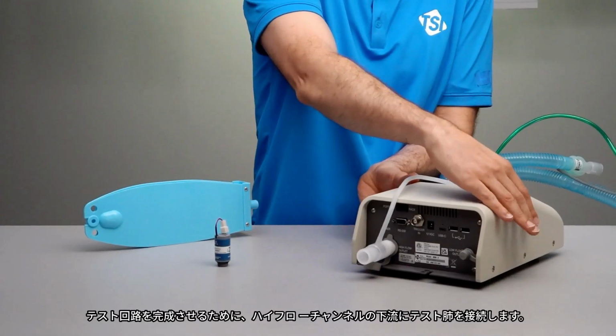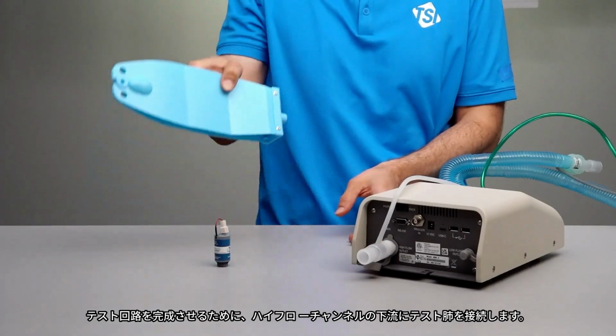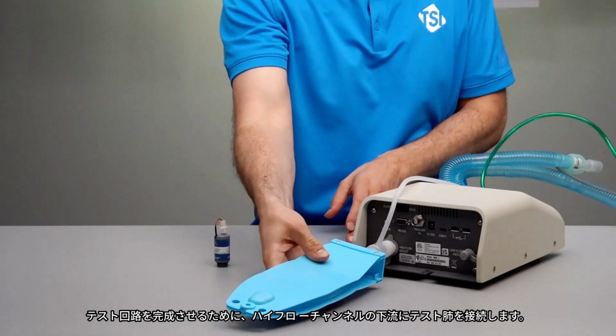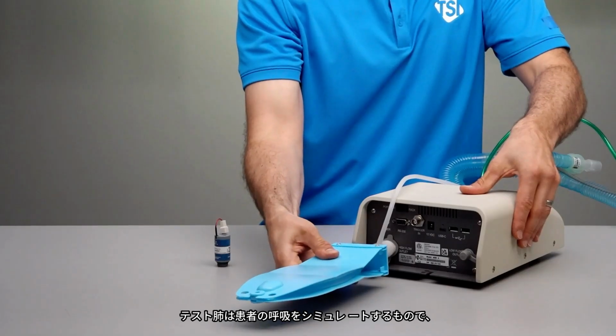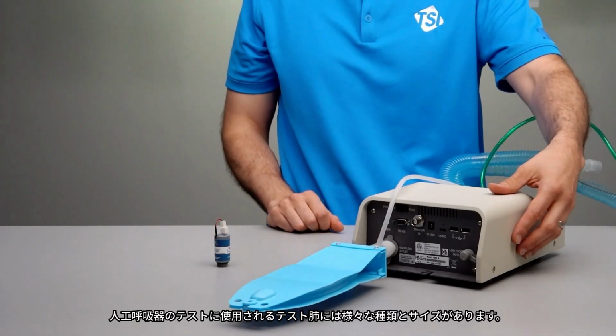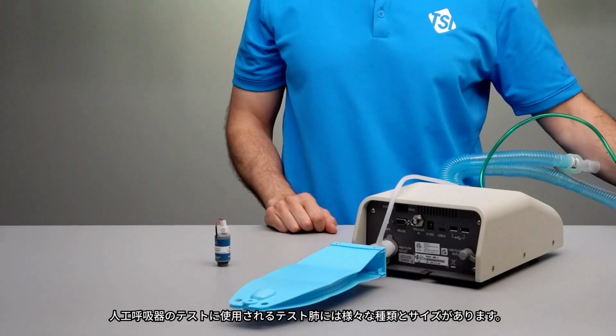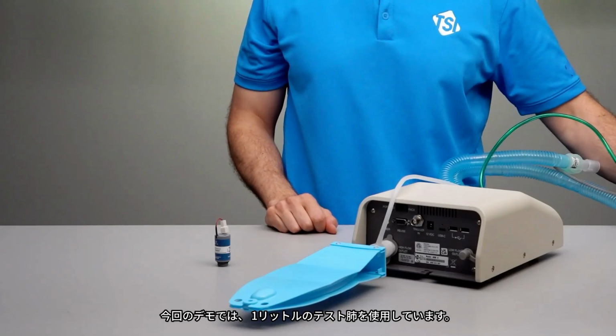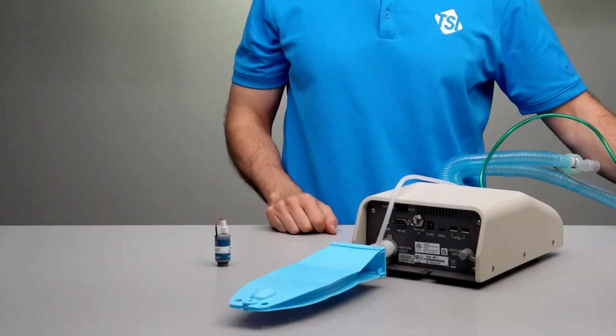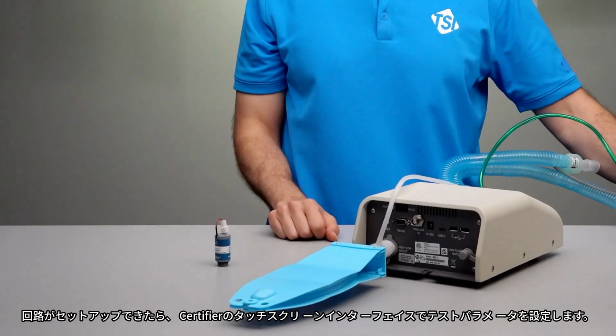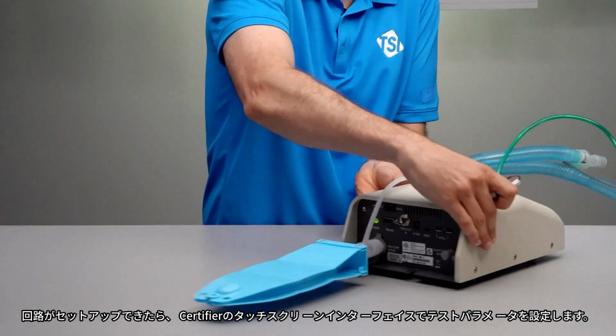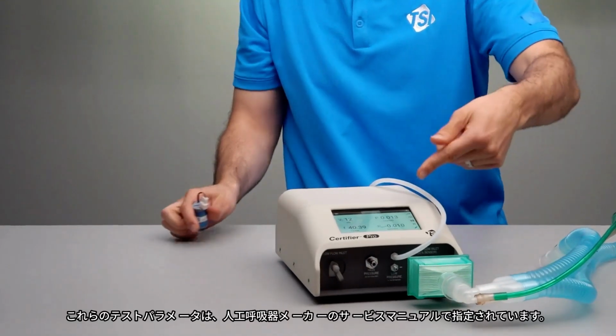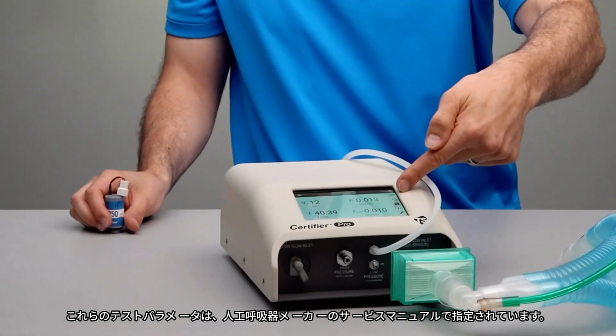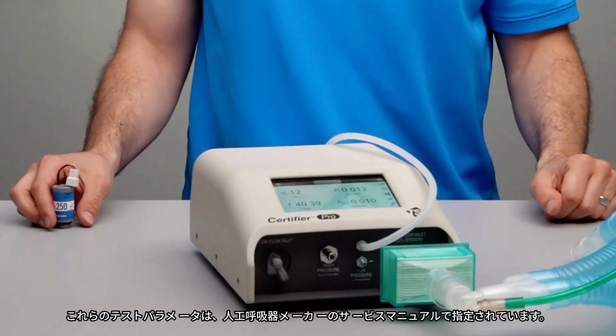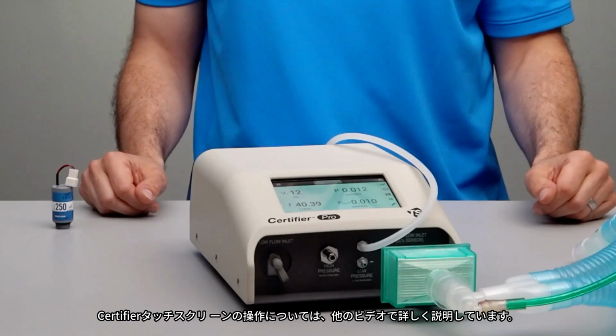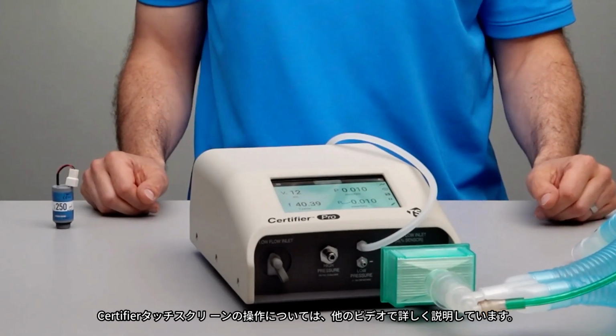To complete the test circuit, we will connect the test lung downstream of the high flow channel. The test lung simulates a patient's breathing, and there are a variety of different types and sizes of lungs that are used when testing ventilators. For our demonstration, we're using a 1-liter test lung. After the circuit is set up, you would configure the test parameters on the certifier's touchscreen interface. These test parameters are specified by the ventilator manufacturer in their service manual. Learn more about operating the Certifier touchscreen in other TSI videos.